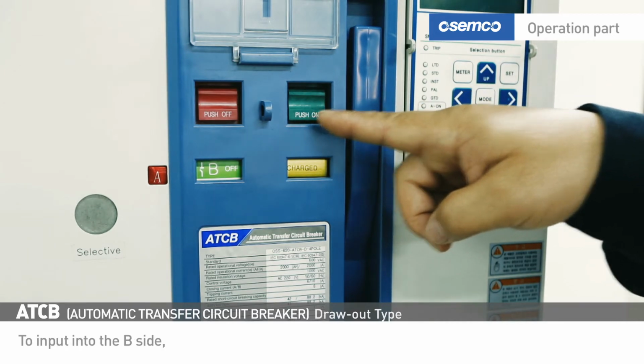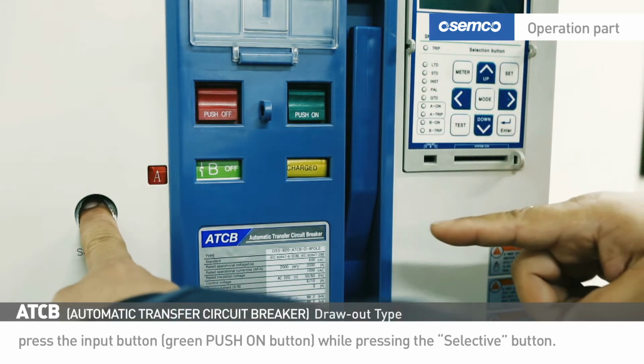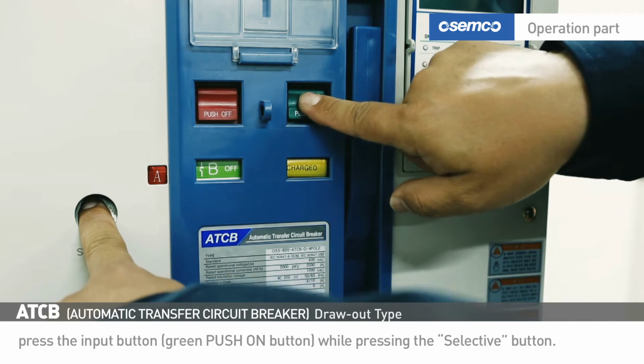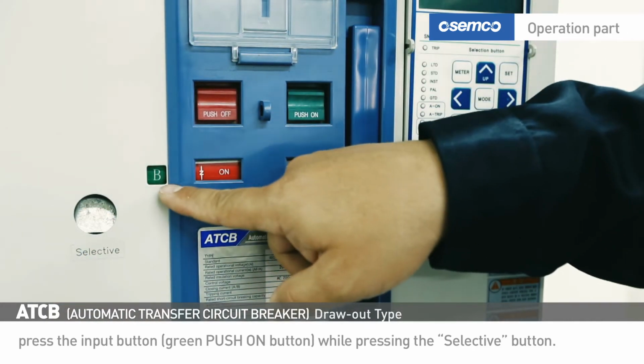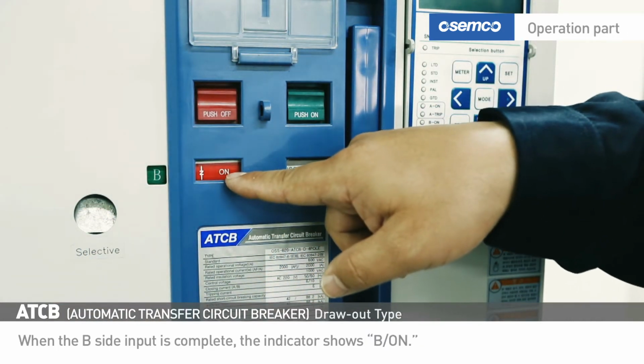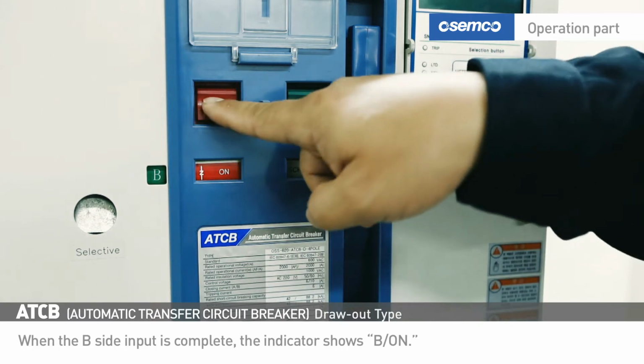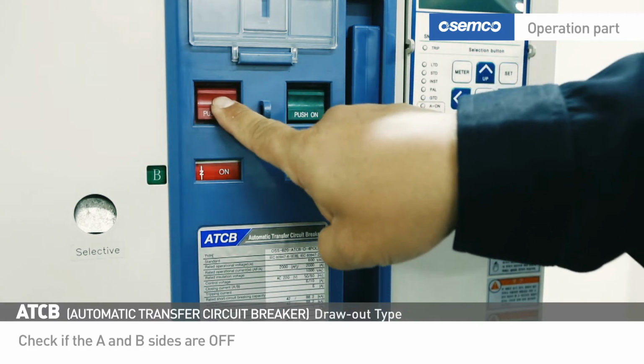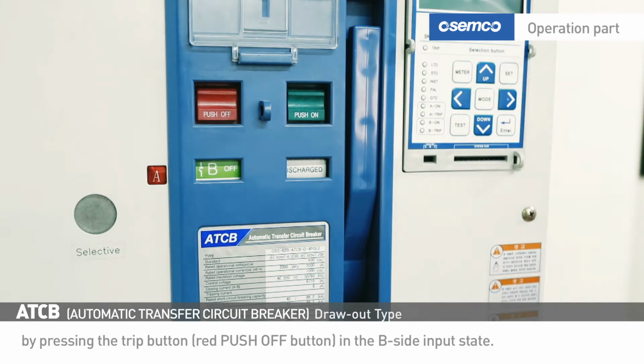To input into the B side, press the Input button, green Push-On button, while pressing the Selective button. When the B side input is complete, the indicator shows B on. Check if the A and B sides are off by pressing the Trip button, red Push-Off button, in the B side input state.